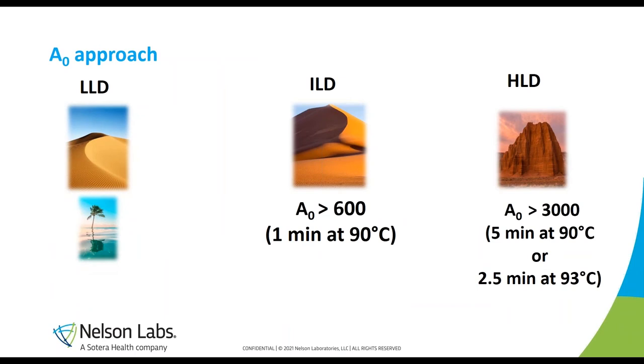With the A₀ approach, low level disinfection is essentially a mirage — just don't go there. For intermediate level disinfection, specifically when protecting healthcare users moving devices to sterilization, you need an A₀ value above 600, generally achieved at 90°C for one minute. For high level disinfection, the A₀ method must be above 3000 — five minutes at 90°C or two and a half minutes at 93°C. In Germany, they always want A₀ above 3000.